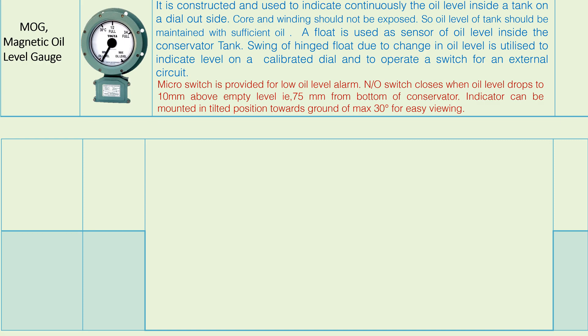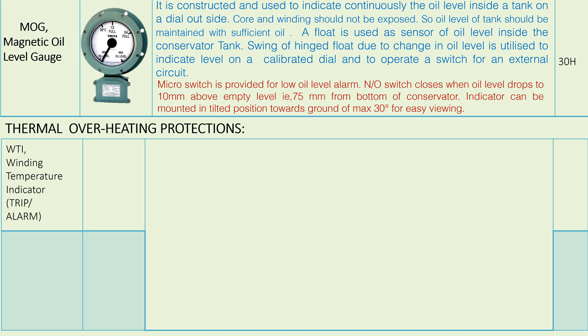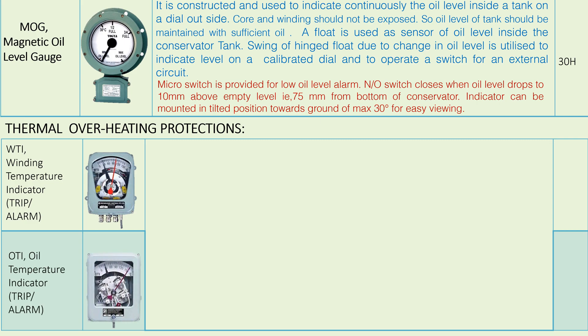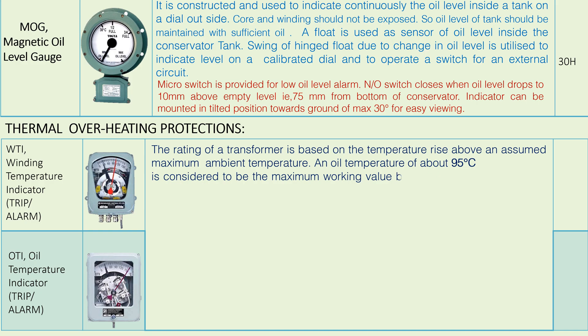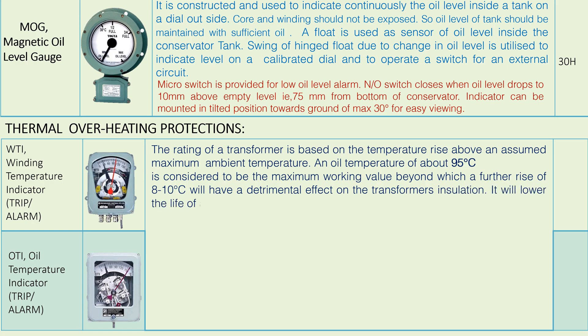Thermal overheating protections — WTI (Winding Temperature Indicator) alarm and trip, OTI (Oil Temperature Indicator). The rating of a transformer is based on the temperature rise above an assumed maximum ambient temperature. Winding temperature and oil temperature of about 95 degrees Centigrade is considered to be the maximum working value, beyond which a further rise of 8 to 10 degrees Centigrade will have a detrimental effect on the transformer insulation and will lower the life of the transformer if sustained.